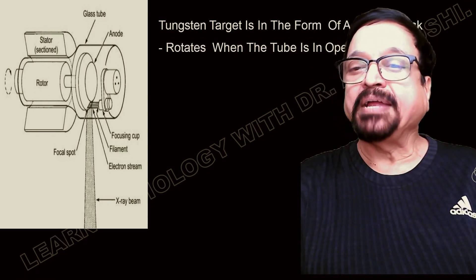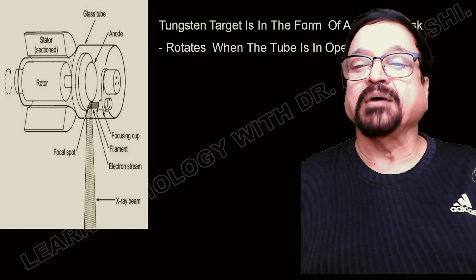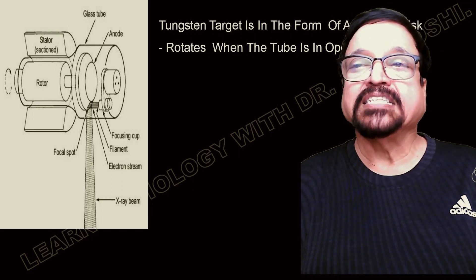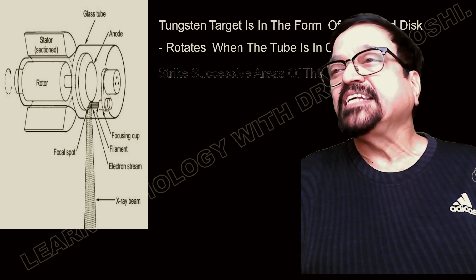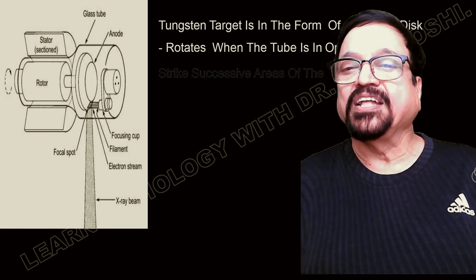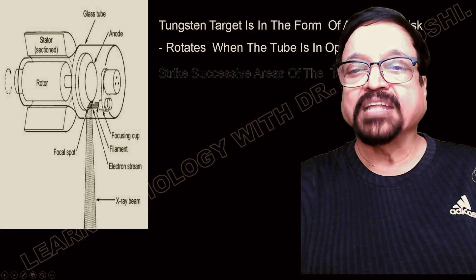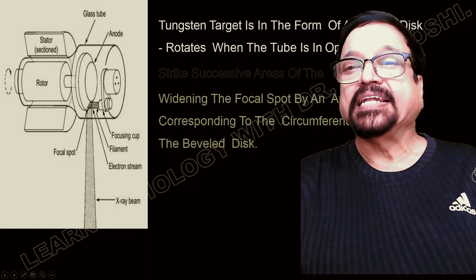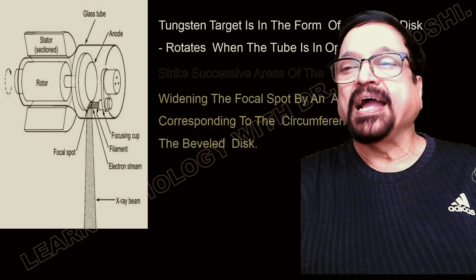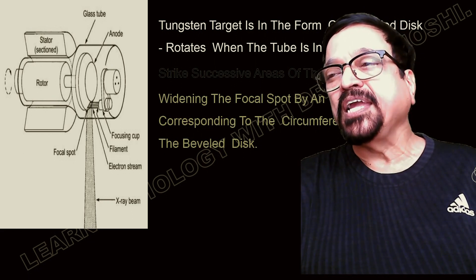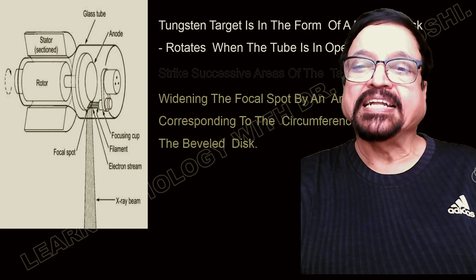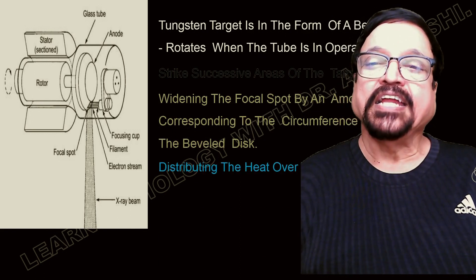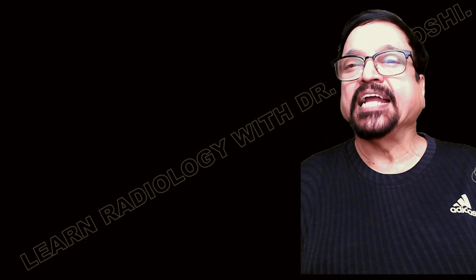There are different videos made for the filament, the focusing cup, and the electron stream — how it is governed and streamlined. The tungsten target is a beveled disc so different areas are getting exposed. Widening of the focal spot corresponds to the circumference of the beveled disc, and therefore heat is distributed over an extended area.